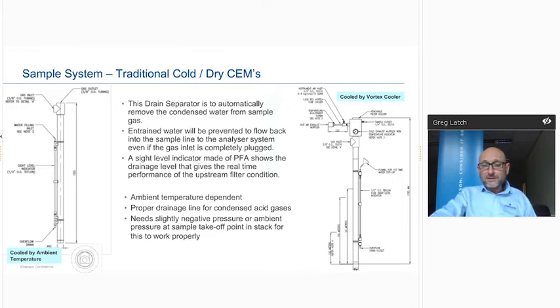There are other technologies available, for example, things like a Nafion dryer and the likes. I absolutely love that technology. The PermaPure membrane, for example, works on, as they say, relative vapor pressure to purge and dry the sample. The comment I can add to that, though, is you're only as good as your dry air purge. So if you've actually got a very poor air supply, the efficiency of that PermaPure membrane technology is not, as I say, up to scratch. Therefore, you will get carryover. And that is a very big challenge then for your downstream sample handling systems. And then from there, you can have challenges with your analyzer.